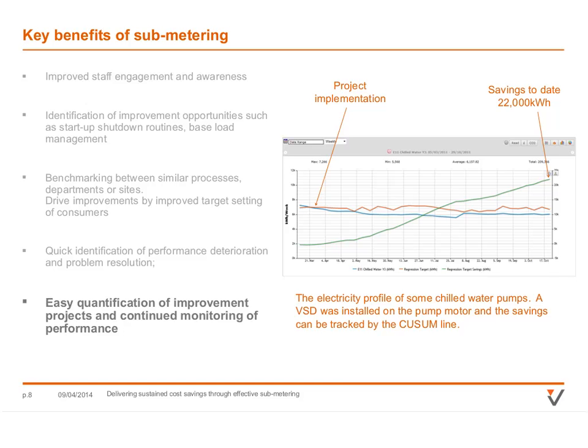This graph shows a system for some chilled water pumps, where we installed some VSDs, and that happened just at the start of the graph. There's a red line and a blue line. The blue line is actual consumption, and the red line is expected consumption given historical usage. What we've shown is that actual consumption drops well below expected consumption for a period of time.